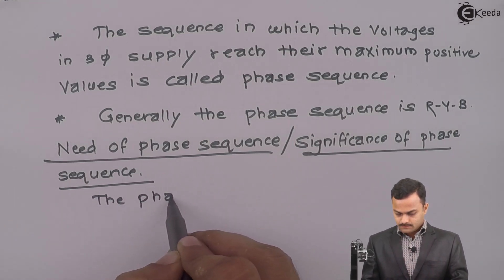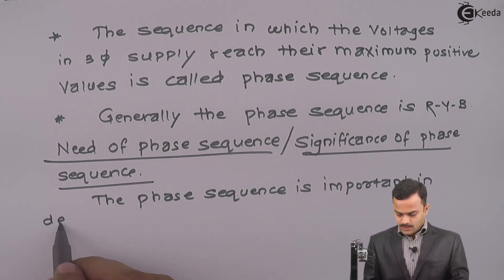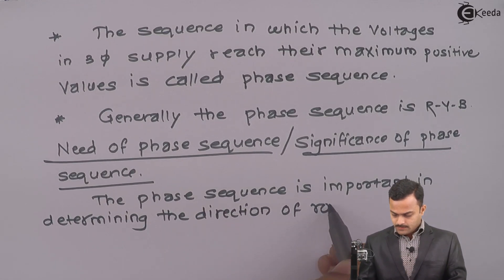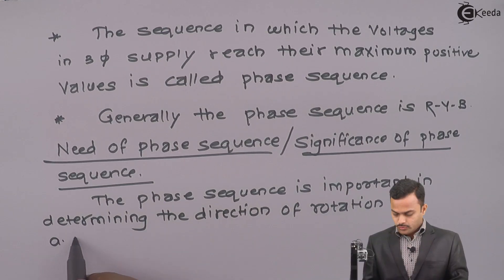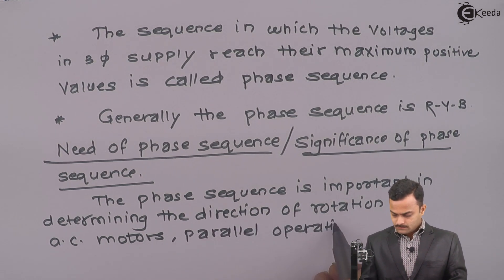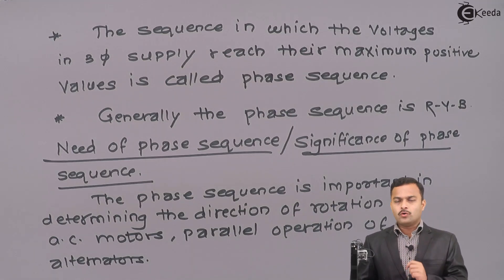The phase sequence is important in determining the direction of rotation of AC motors and parallel operations of alternators. It is very important to note down in which direction motor is moving and if you change the phase sequence the direction of rotation of AC motor will get reverse. So, for this reason knowing the phase sequence and connecting motor as per the phase sequence is must. Thank you.